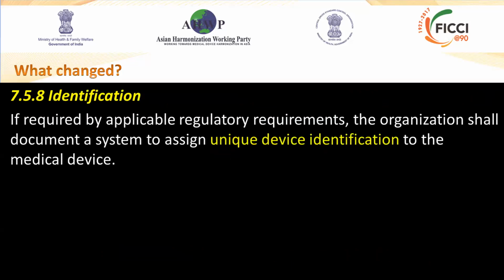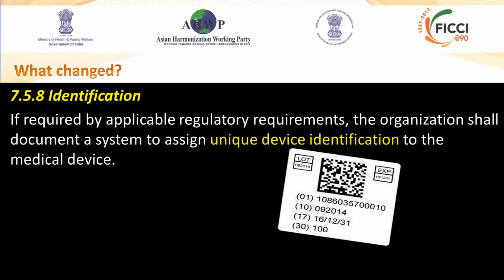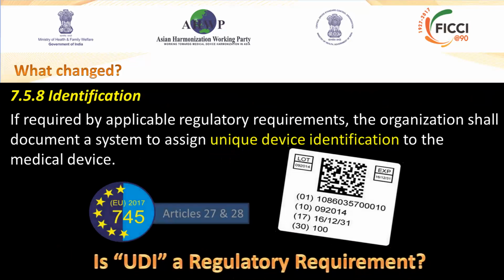A little bit more focus on identification, and this is something that's developed recently, just within the last few years with the US FDA's unique device identification. So if required by applicable regulatory requirements, the organization shall document a system to assign unique device identification, UDI as we call it. So UDI, where it's a regulatory requirement, needs to be integrated into the identification process for the quality management system to meet 13485.